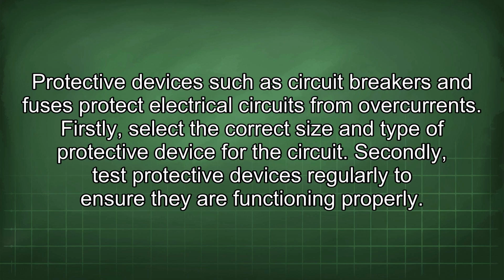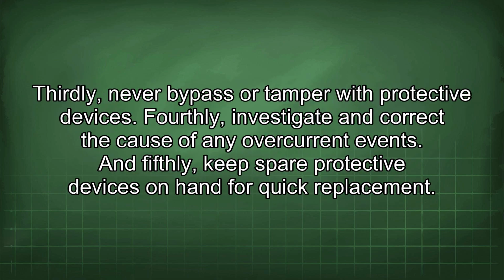Protective devices such as circuit breakers and fuses protect electrical circuits from overcurrents. Firstly, select the correct size and type of protective device for the circuit. Secondly, test protective devices regularly to ensure they are functioning properly. Thirdly, never bypass or tamper with protective devices. Fourthly, investigate and correct the cause of any overcurrent events. And fifthly, keep spare protective devices on hand for quick replacement.